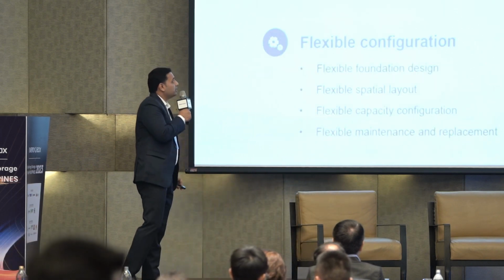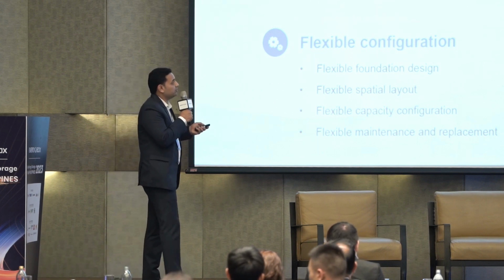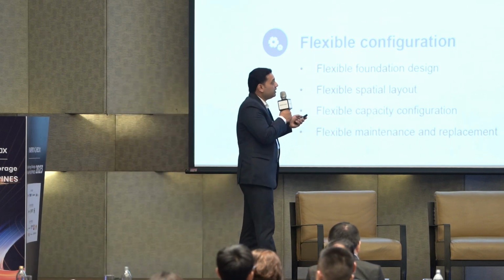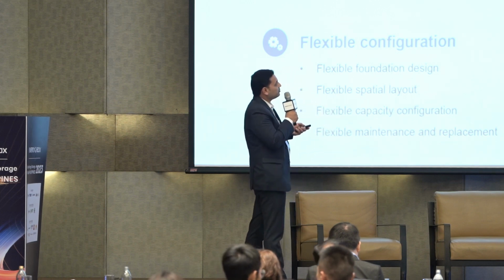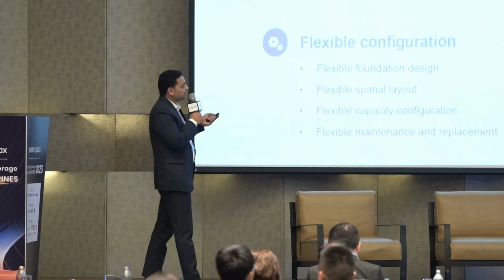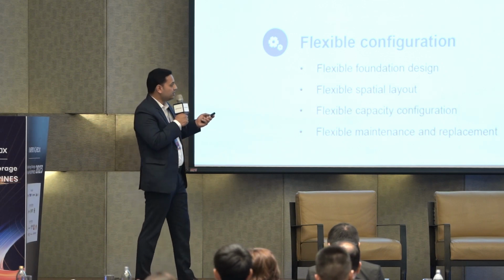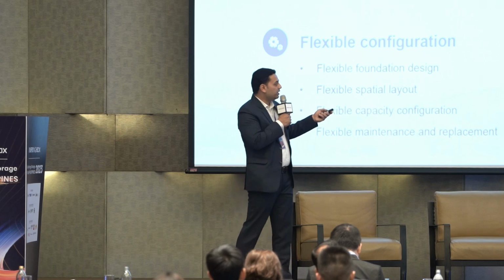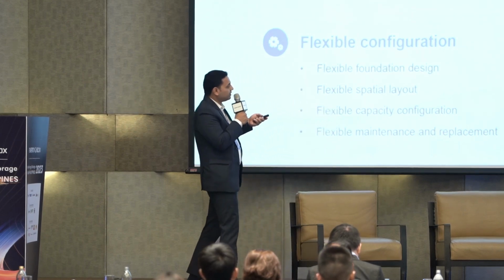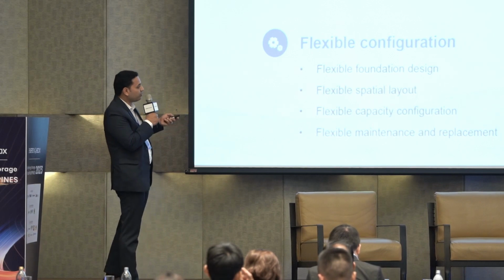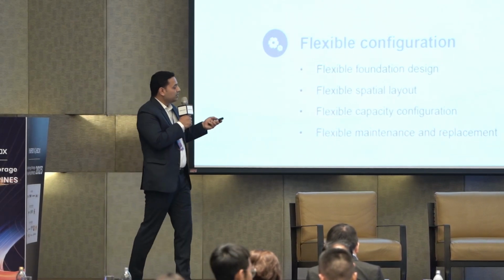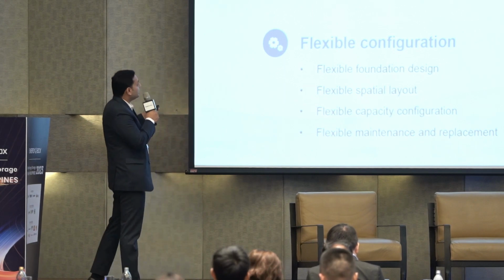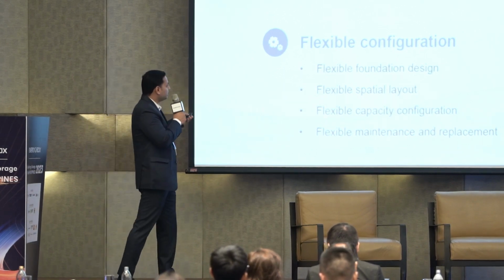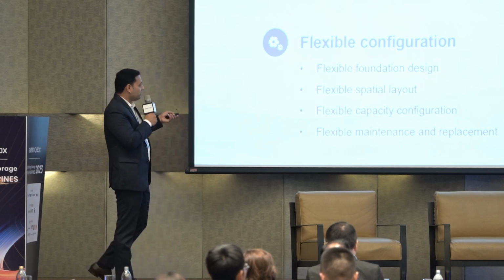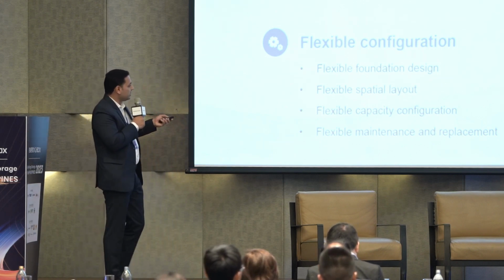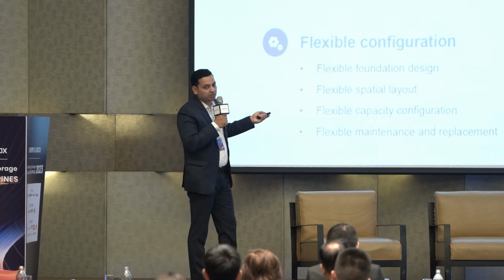Liquid cooling battery cabinet with the safety protection of liquid cooled leak proof design, integrated liquid guide tank, real-time liquid leakage protection, efficiency improvement, as I mentioned, plus 7% more usable capacity of the batteries, plus 20% longer operating cycle of the batteries, a smaller temperature difference, less than 3%, higher energy density, plus 24%, low power supply cost, which is minus 9%. Then since it is having the flexible configuration, you can have flexible foundation design, flexible spatial layout, flexible capacity configuration, and flexible maintenance and replacement option.